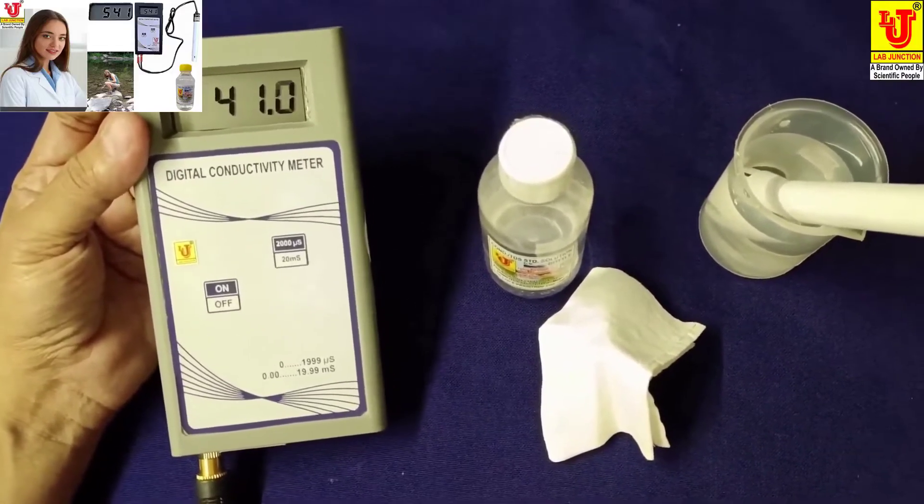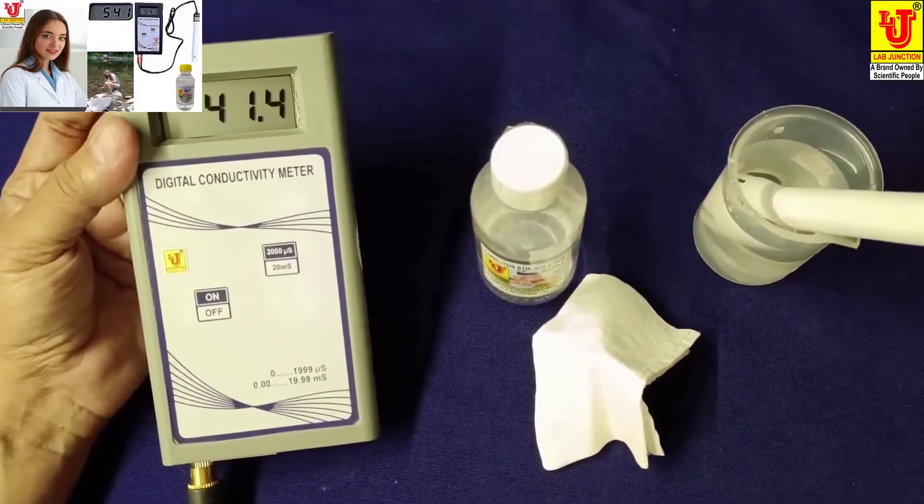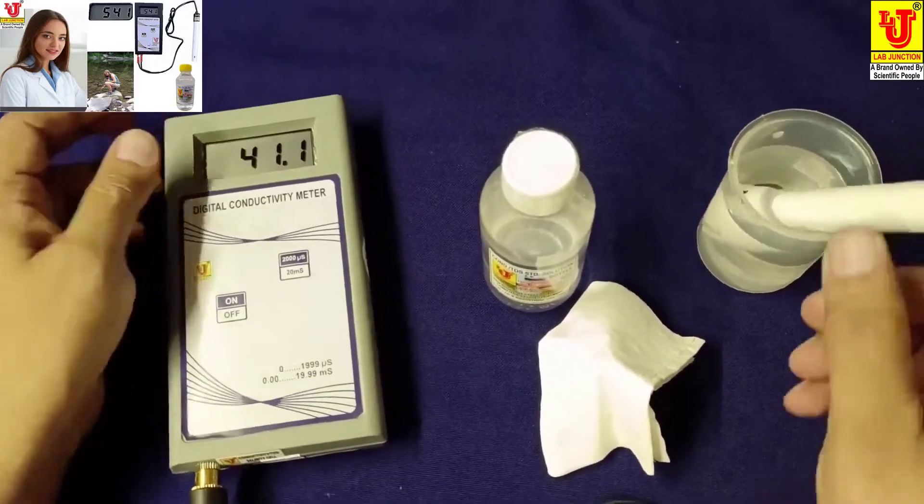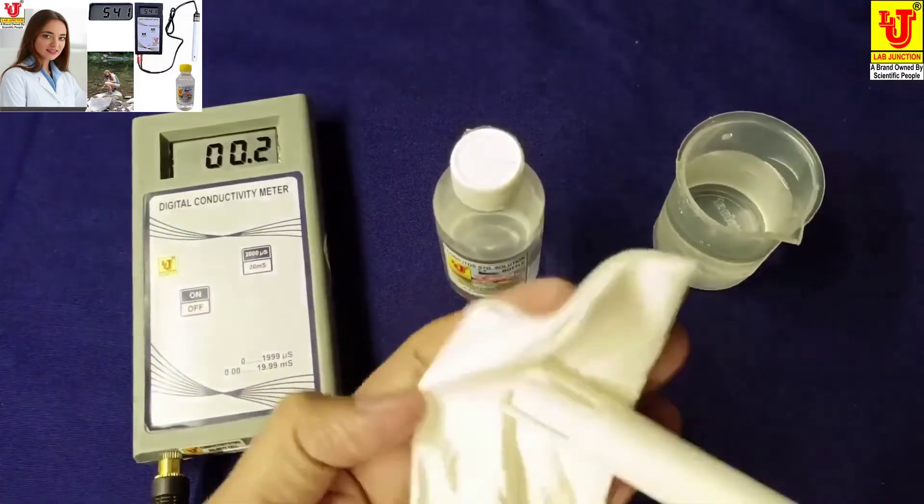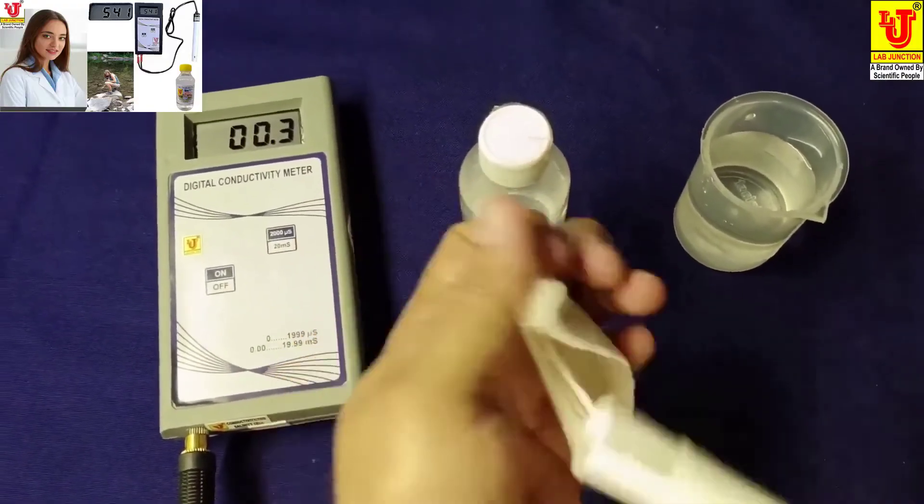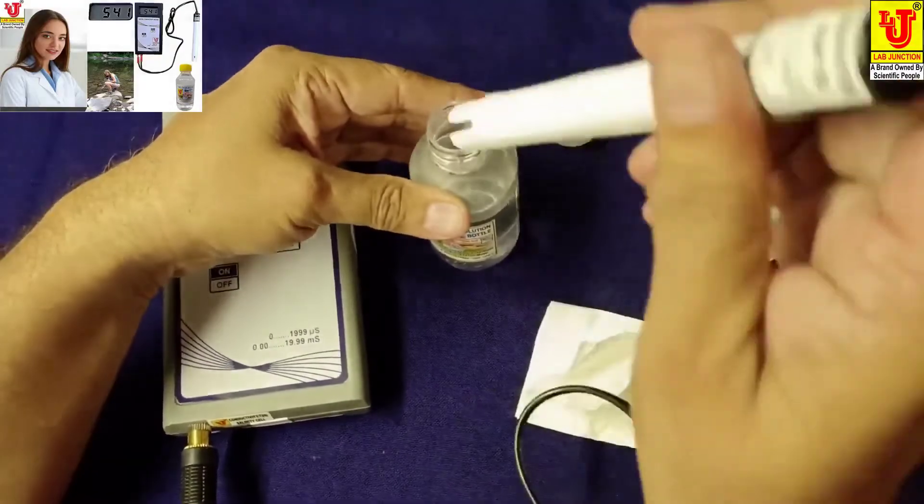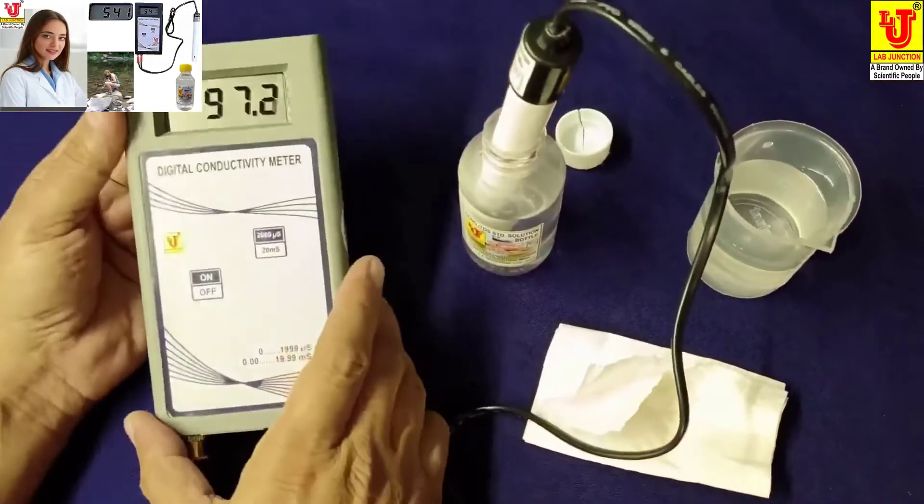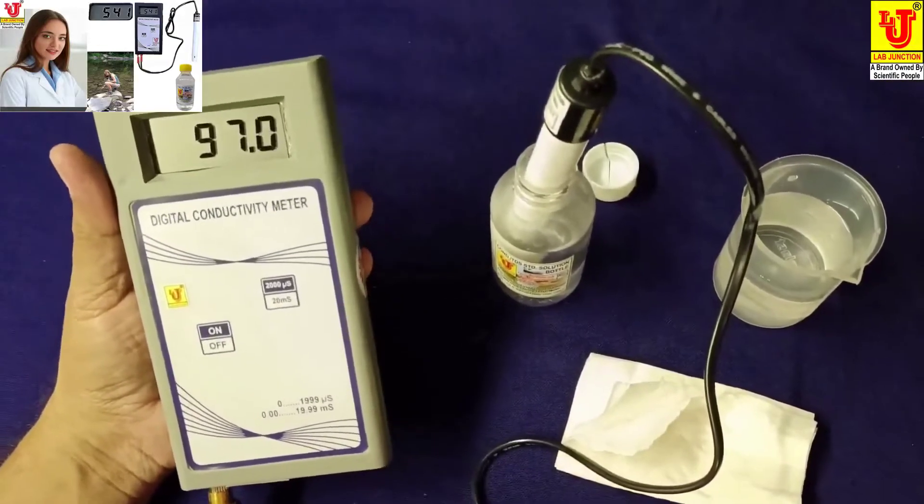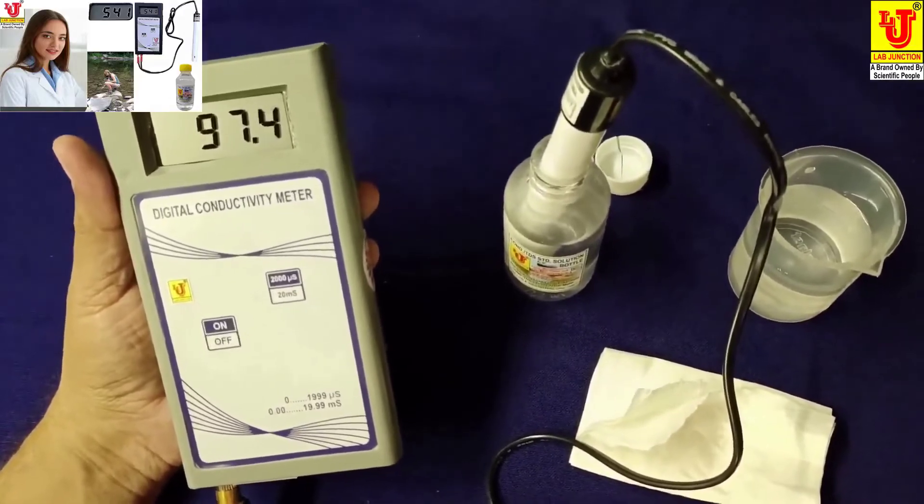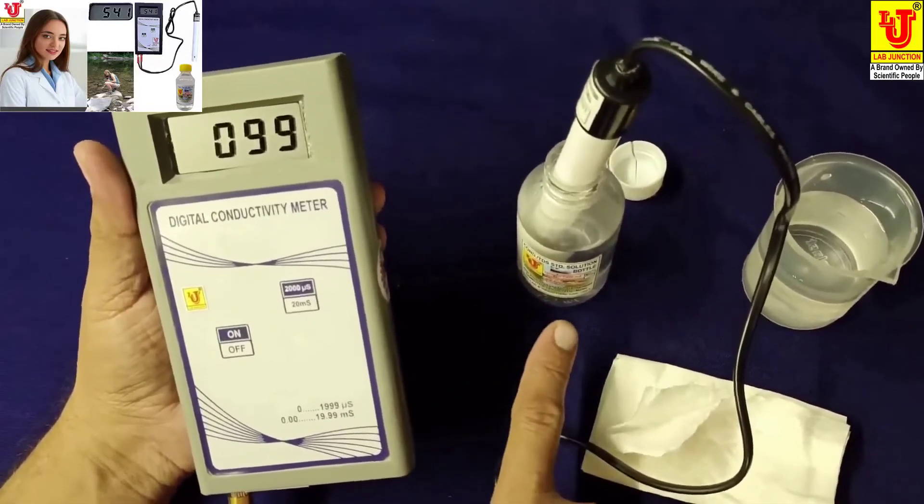Now if you want to calibrate with conductivity solution, then what you will do? Directly open the standard solution bottle, dip your electrode in the standard solution. Change the range to 20, now this is 1 millisiemens. Now this is already calibrated.